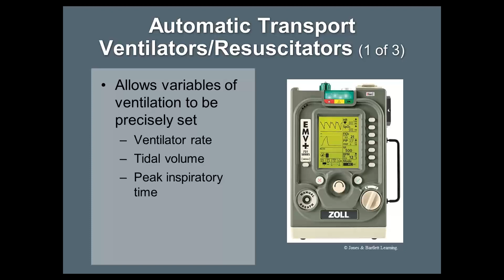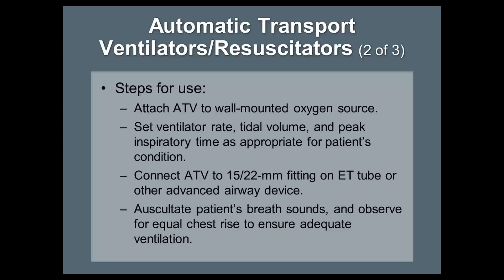Now, like I said, the advanced ventilators go up to where you deal with people with ARDS, or acute respiratory distress syndrome. They'll swap back and forth between modes. Let me show you this. On the bottom right here, it shows mode and it says AC. That's assist control. That's going to give a breath every how many seconds you set it to, regardless of what the patient is doing. There's another mode you can check called SIMV. Some patients have some respiratory effort, and every time the patient goes to take a breath, it will give them a breath. But if a patient doesn't take a breath, say in 5 seconds, it'll go ahead and give one automatically. So it has a set rate, but it's triggered by the patient, whereas AC is not. And that's usually patient selective, depending on what they might need.